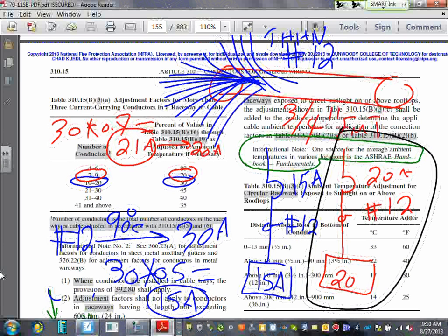The best design, when you build a system like this, is that out of that panel you come up with multiple 3/4 inch conduits. And then you load each 3/4 inch with 9 conductors. Now with these 9 conductors, I can co-feed number 12, I can feed receptacles and lights out of them if they're on the same panel. Each circuit will be a hot and a neutral, and we can share a neutral between 3 hots. So each 4 of them will be carrying 3 circuits, basically: hot 1, hot 2, hot 3, phase A, phase B, phase C, and a neutral. Here's 3 circuits. So if I have 9 conductors, I need 4 and 4, so that will give you 8 conductors.